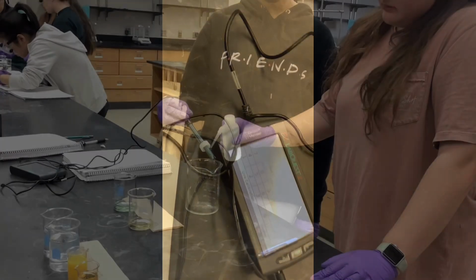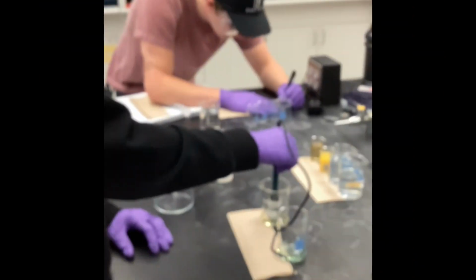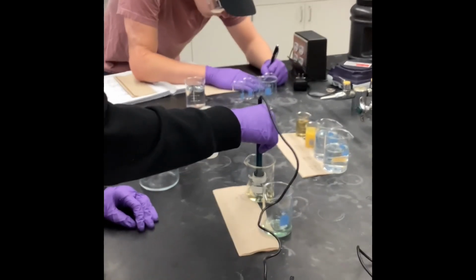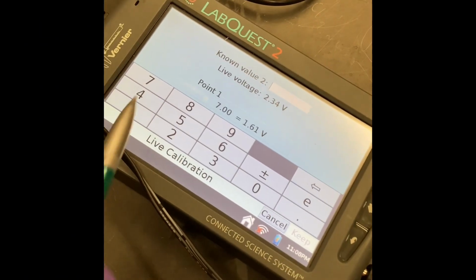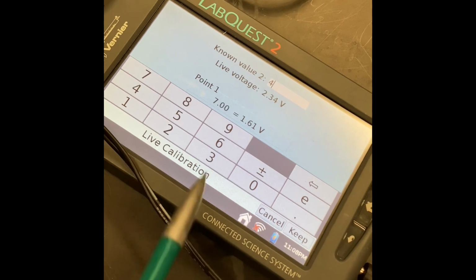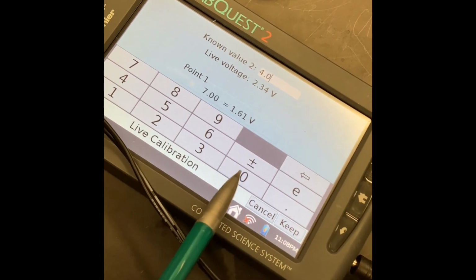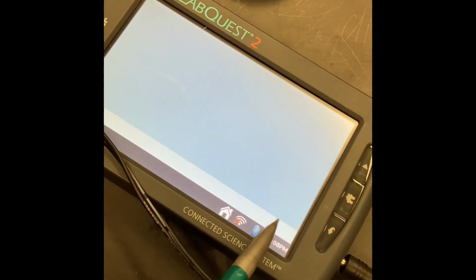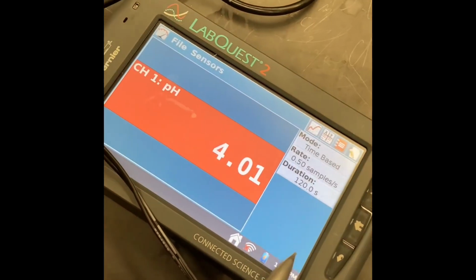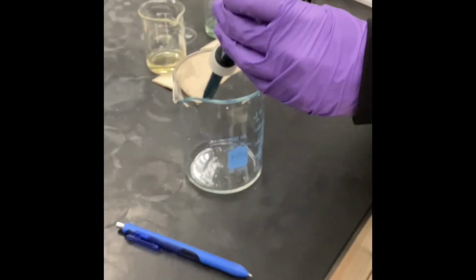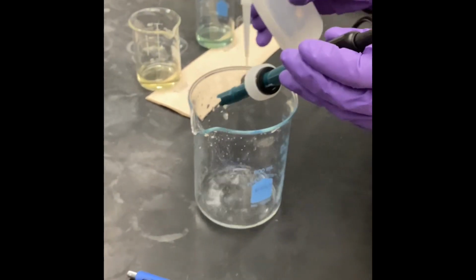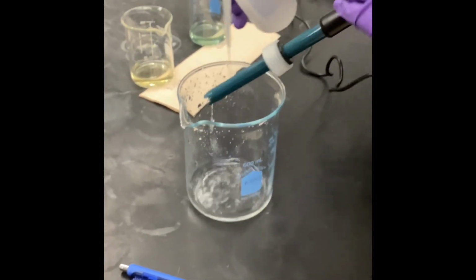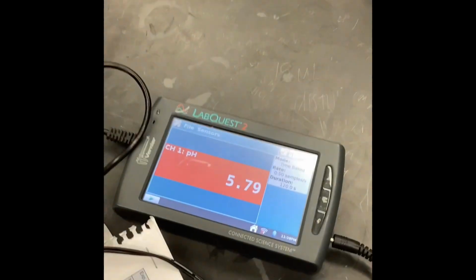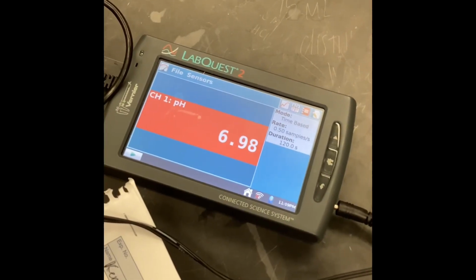Now it is time to do our second buffer solution, so we will clean that off, and then we will stick it in the buffer 4, and then we will wait for the live voltage to even out again, and we will type in 4.00 for our pH 4 buffer. Now we will click Calibrate Now and press OK, and now it should be calibrated, but we need to check, so we need to clean off our pH probe and stick it back in the pH 7 buffer, make sure it is showing up as 7. And it is, so now it is time to start our experiment.